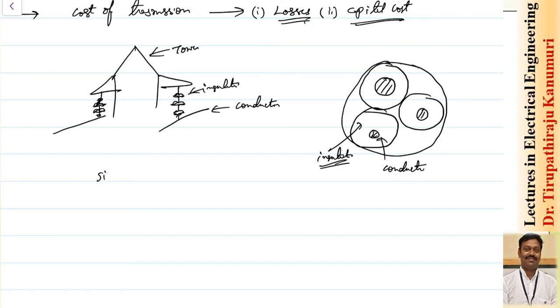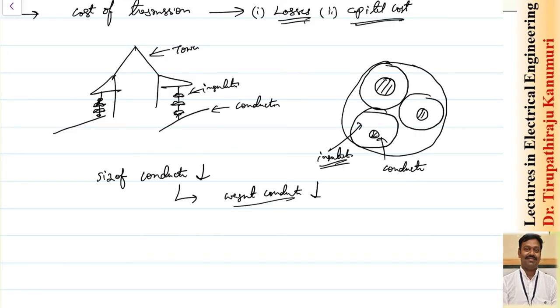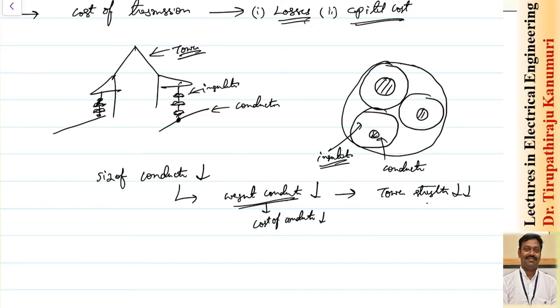If the size of the conductor is decreased, the weight and volume of the conductor decrease, so the cost of the conductor decreases. When the weight of the conductor decreases, the entire weight on the tower decreases, so the required tower strength decreases, reducing the cost of the tower. This saves cost in multiple ways.